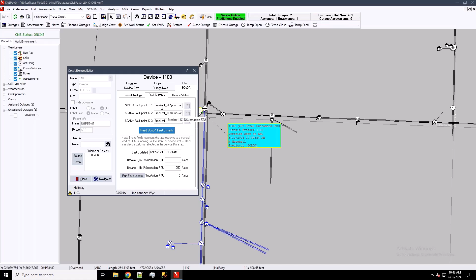So that was another multi-speak request. Our dispatch system made a request and said, can you give me the SCADA fault values by point ID? So we reached out and asked for the fault amps by these particular point IDs that I have mapped. And you can see we've got 1,250 fault amps on B phase, and here's our timestamp. So what this will let us do is run fault locator.